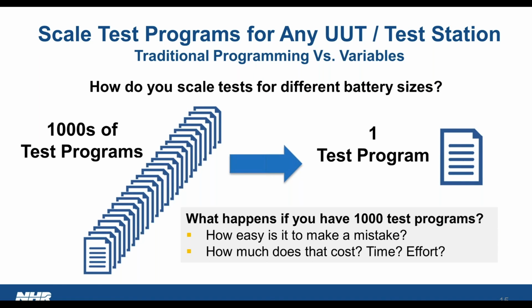When you consider traditional programming, if I needed to do something simple like a pulse discharge test, or discharge a battery at its rated rate of current, for most cyclers you actually have to produce a different test, even though it's for the same basic function, that's scaled appropriately for each different application or each different battery. That combination can produce a matrix of hundreds to literally thousands of test programs.